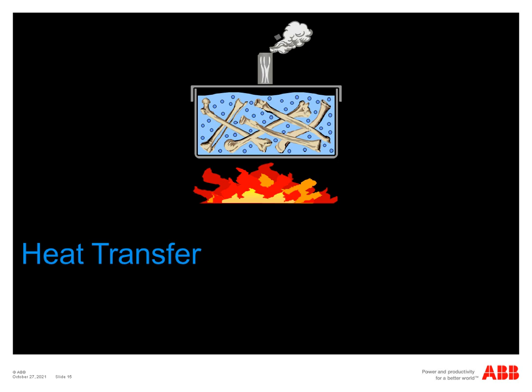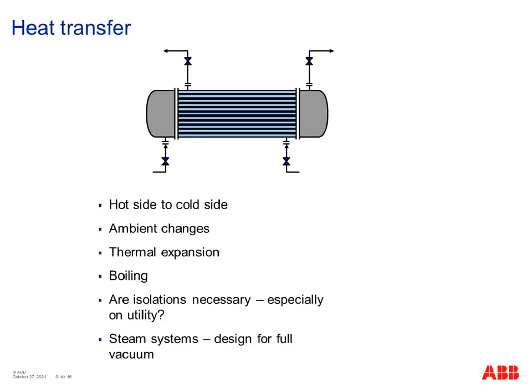Moving on to heat transfer, leading to overpressure. So the key question here is, if your exchanger is blocked in, can the hot side cause an overpressure in the cold side? So the energy from the hot side moving on to the cold side, which is blocked in, can that cause overpressure in the cold side? This could also be caused by ambient changes, so solar gain from the environment.